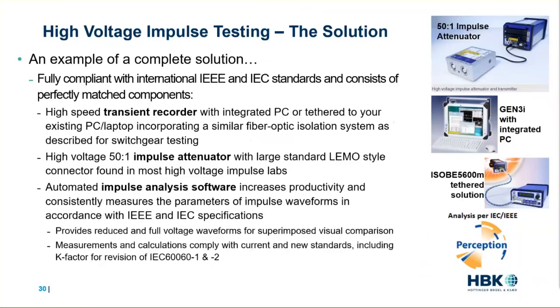Then you have automated impulse analysis software, and this is going to increase your productivity and consistently measure the parameters of impulse waveforms in accordance to the standards for IEEE and IEC. It's going to provide you reduced full voltage waveforms for superimposed visual comparison, and you can even make measurements and calculations that comply with current and new standards, including the K factor for the revision of the IEC standard.